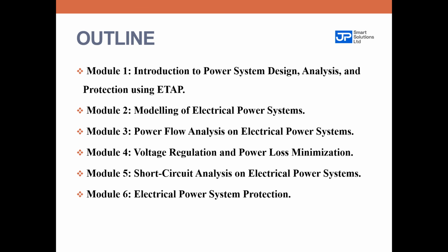Then we move on to Part B of Module 6, which covers the differential protection scheme. We will explain the concept of a differential protection scheme, and we will have two hands-on exercises: designing a differential protection scheme for a 5 MVA transformer, and designing one for an 11 kV bus bar.